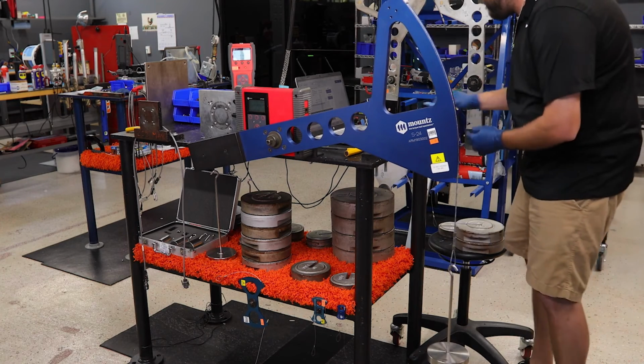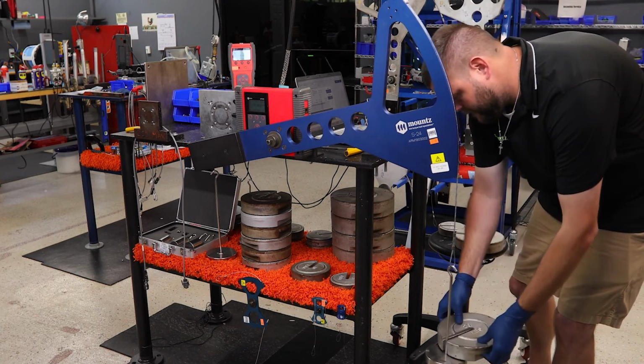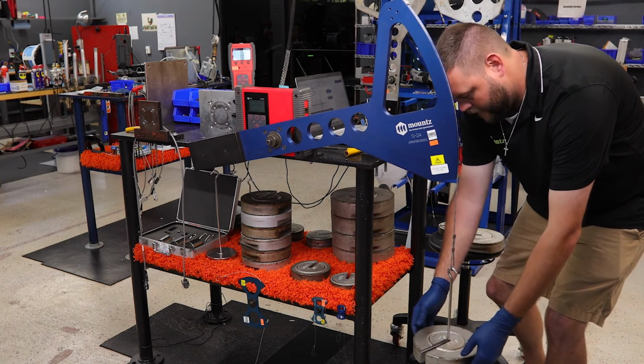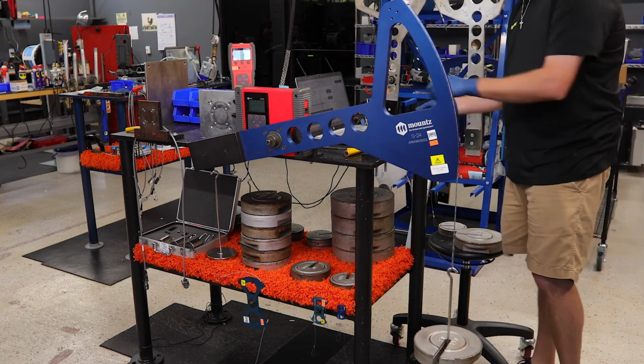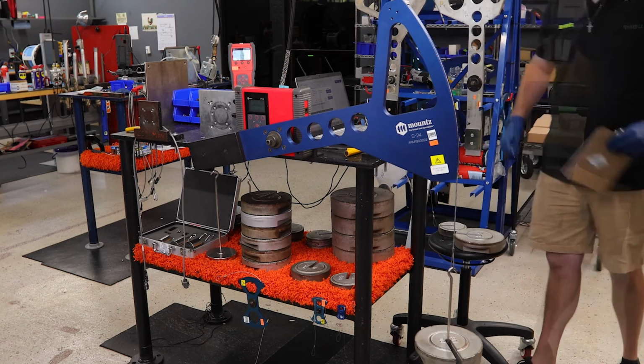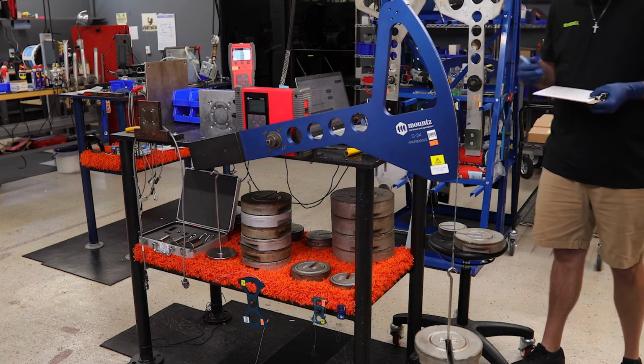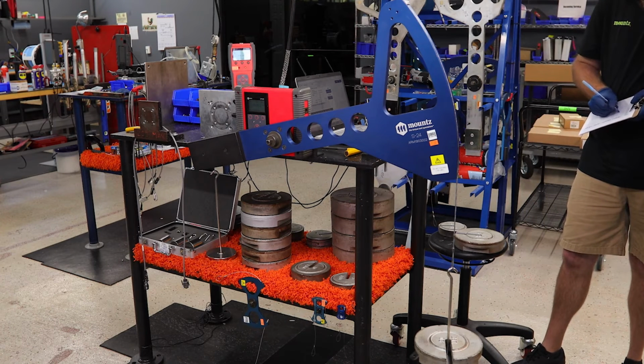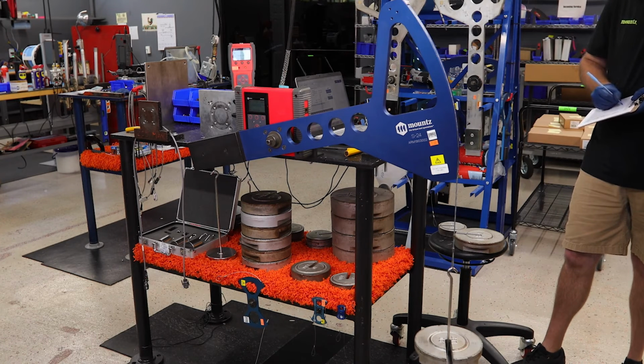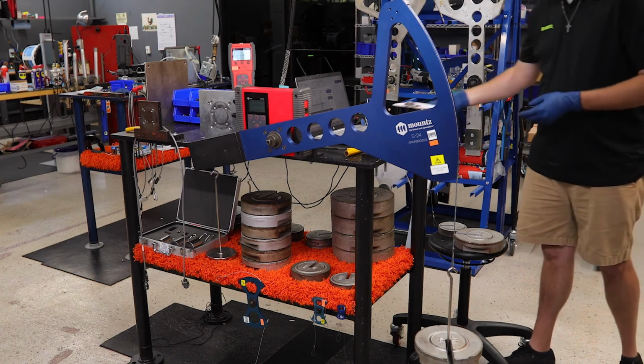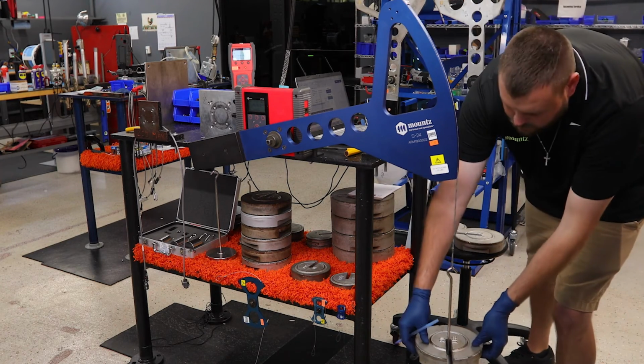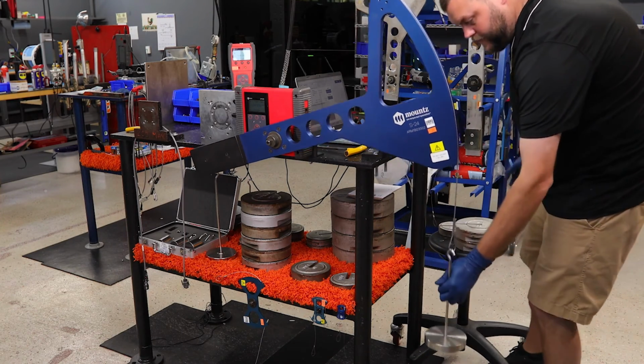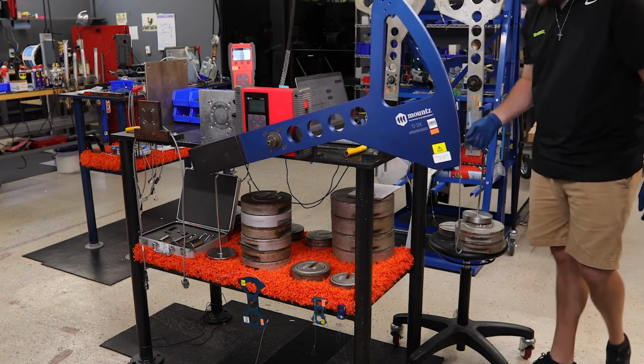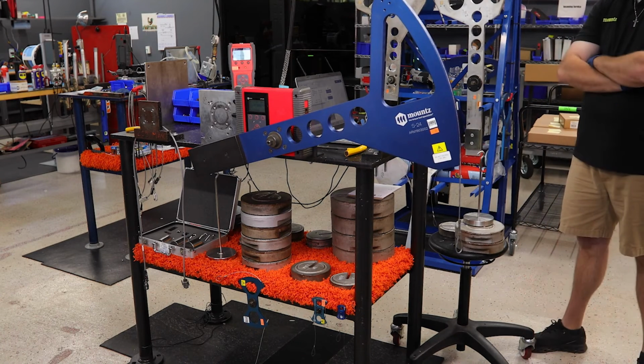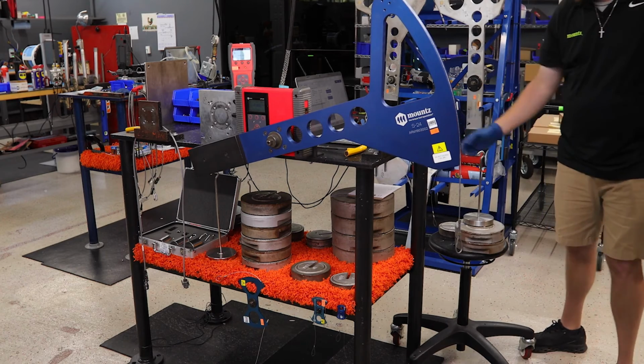So we are now moving on to our 50% for our second reading within the calibration process. And another thing to keep in mind is that we want to make sure that the weight is very still while this process is going on, so there isn't any type of movement deflection that's causing any irregularities within the readings of the process. And so now that the 50% reading has been done, we'll now go ahead and we load back to 100%.